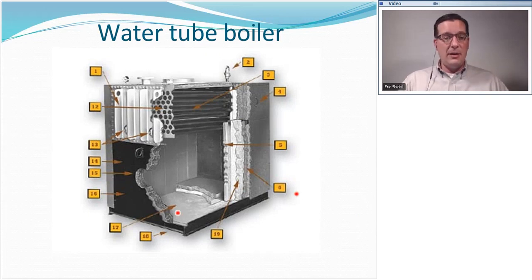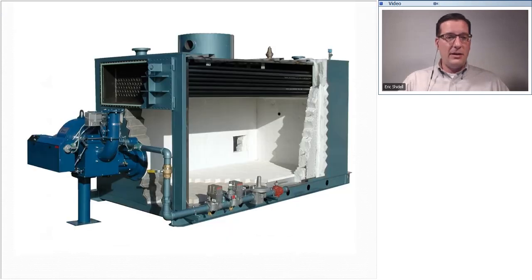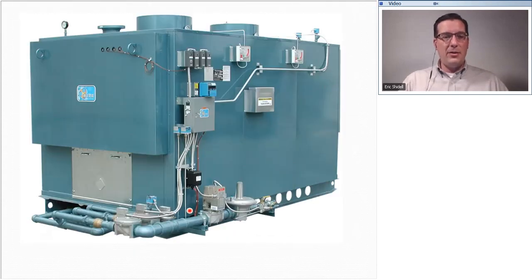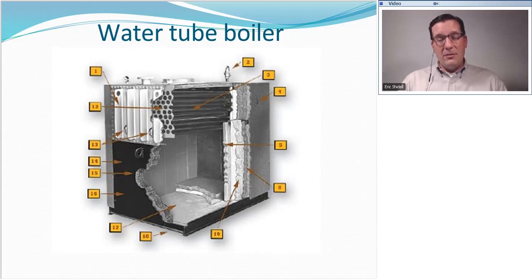Imagine this one would have the sea of burners underneath it. You can't see where the burners are, but imagine this entire floor covered with burners being monitored by a single standing pilot, and that can be a little frightening as far as safety goes, and that's true. But also be aware that if one of these tubes springs a leak, they can be plugged. So that doesn't mean that we have to stop everything, drain the system, and fix or replace that boiler now. Those tubes can actually be plugged and then let the thing run through the heating season and deal with it in the spring or something along those lines. Now, because of that, you may have a boiler that has a significant number of tubes plugged, and that can be a problem.